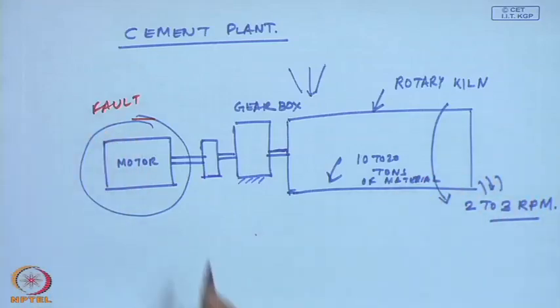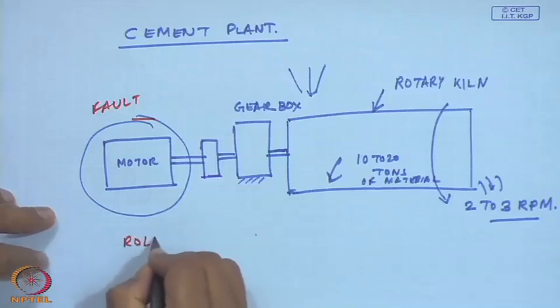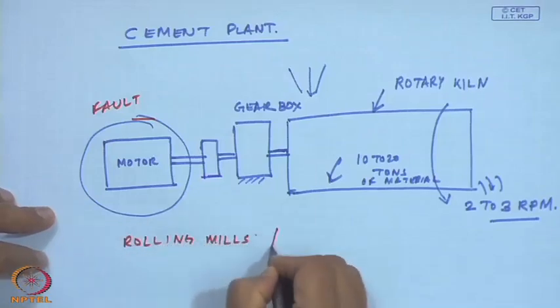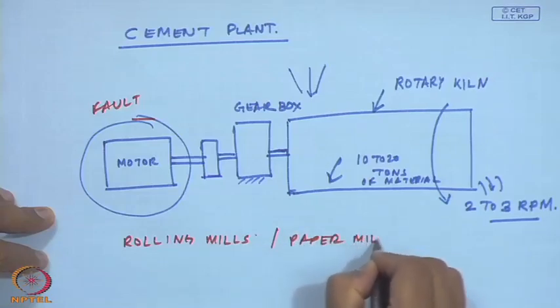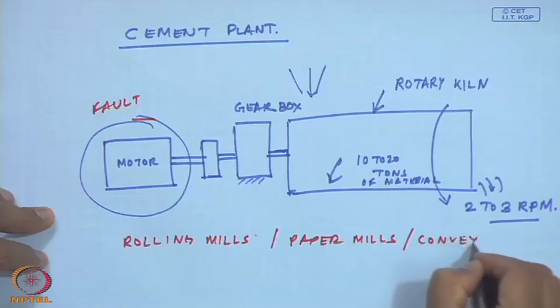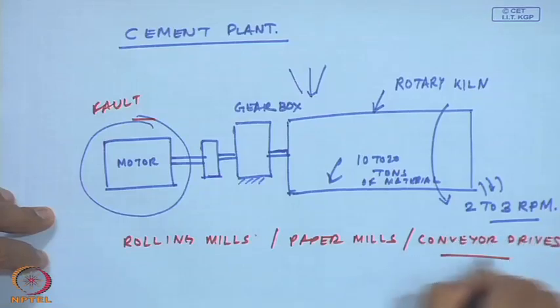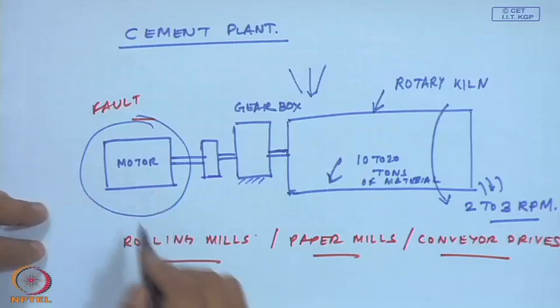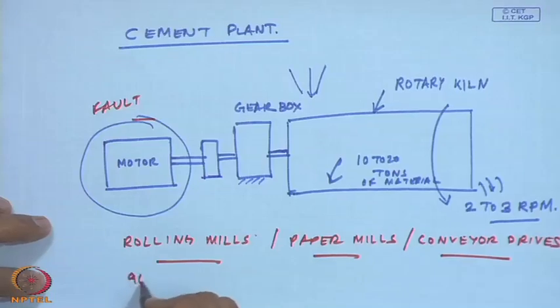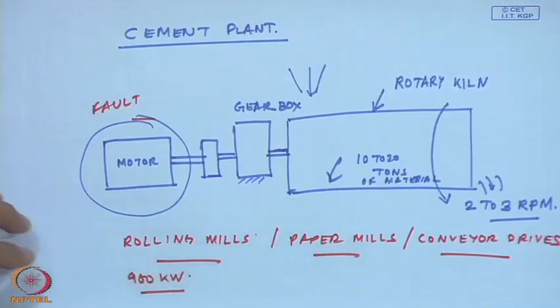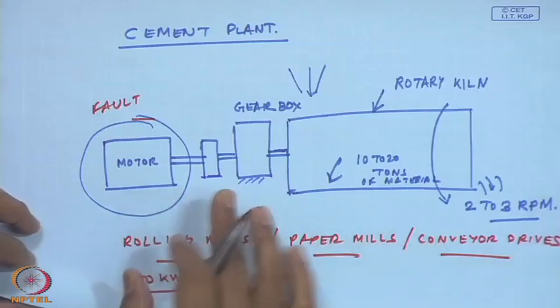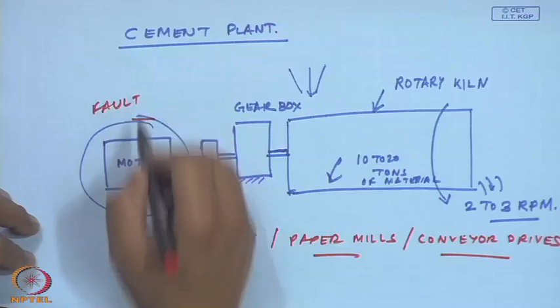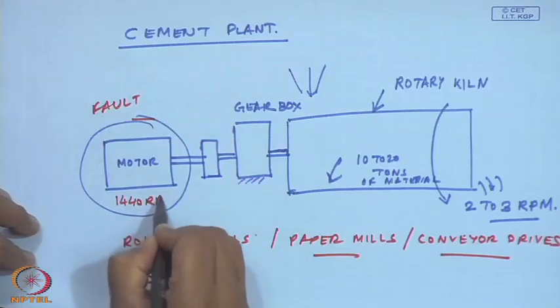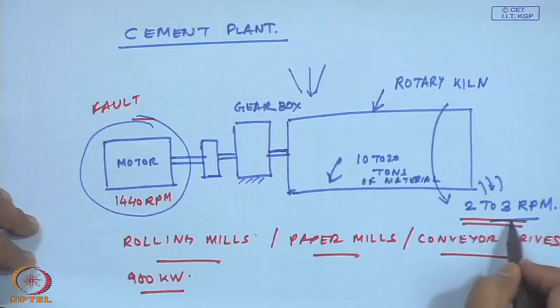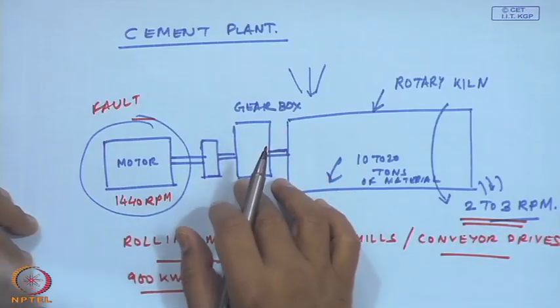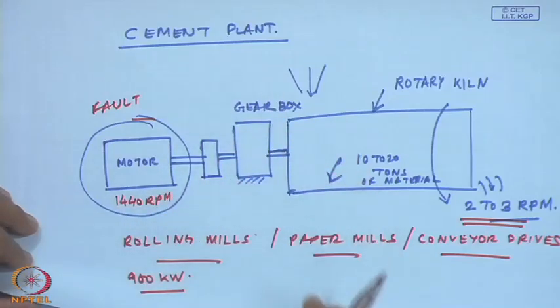So, let us see. This is the case of a cement plant, and the same is true in rolling mills, paper mills, conveyor drives. The powering units are these motors. Motors are usually an AC induction motor, typically 900 kilowatts in power. Of course, there are larger motors we could be using, and they are almost all designed to run at constant speed. And this gearbox, because from an RPM of 1440, you are finally rotating the kiln at 2 to 3 RPM. So, you can imagine the amount of speed reduction being brought about over the gearbox. So, this is a heavy, multi-stage gearbox and so on.